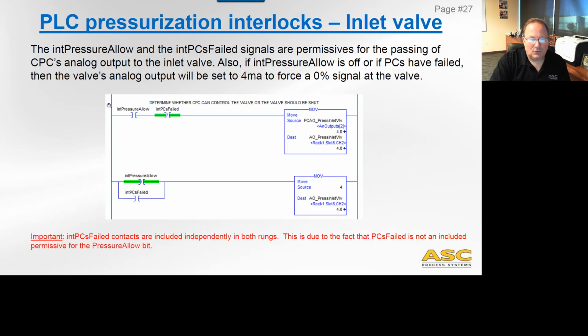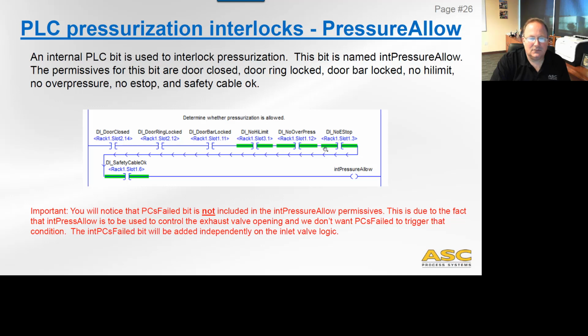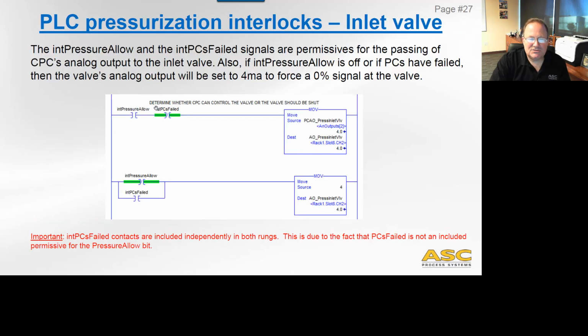So what you'll now see is, for example, for the inlet valve. The pressure allow coil, which we generate here, is used in series and in parallel with the PCs failed. So this is where we're moving the CPC analog signal over to the valve. We allow that to happen if pressure is allowed and we are not having a PC fail condition, okay? If we do have a PC fail condition, we're going to move a 4 to that valve. So that's what shuts that valve down, okay?